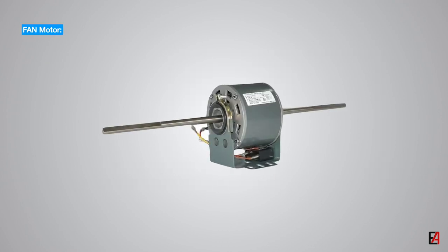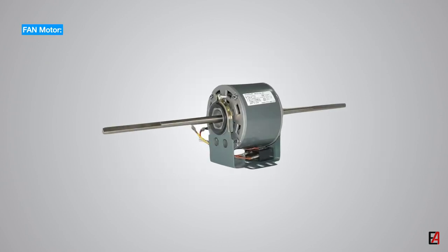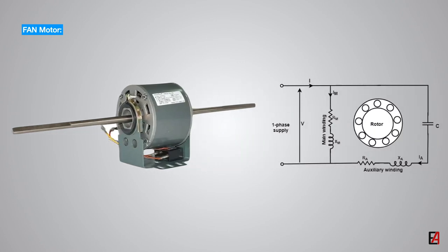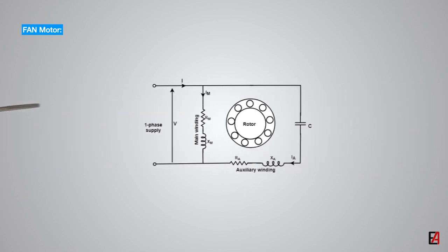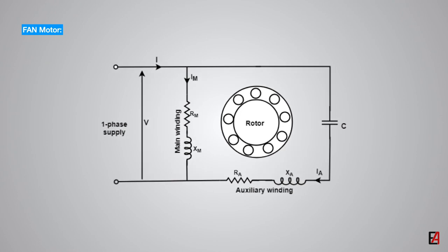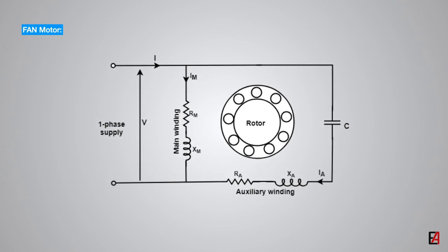The fan motor is typically a permanent split capacitor PSC motor. To use a single-phase power supply, a PSC motor is equipped with two separate windings, main winding and auxiliary winding, with the main winding connected directly to the power supply and the auxiliary winding connected to the main winding via a capacitor.